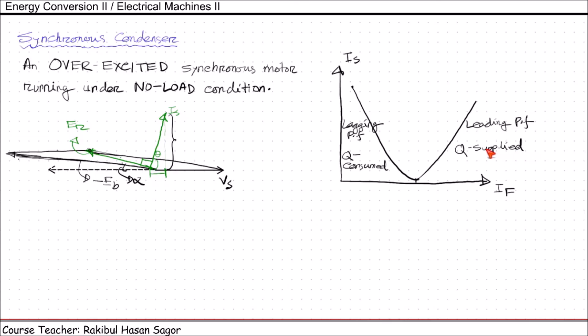Sometimes the synchronous motors are built in such a way that they are made specifically for power factor correction. These machines have shafts that do not even come through the frame of the motor. But nowadays, conventional static capacitors are more economical to buy and those are used more widely than synchronous capacitors or synchronous condensers.